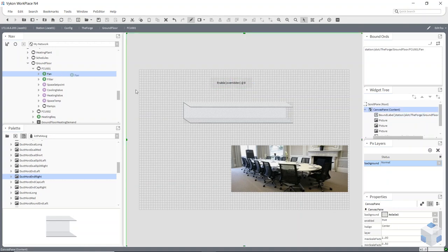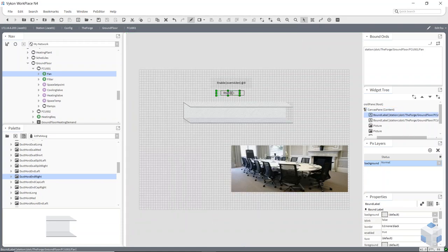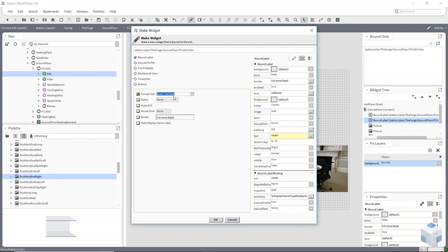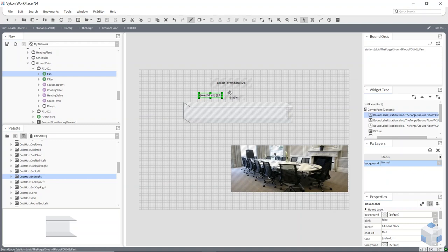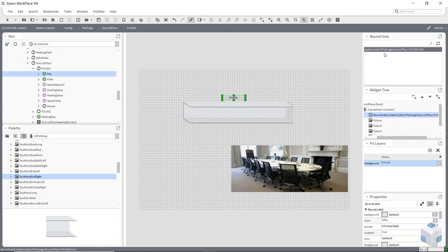If I bring that on again for the same point and change my format to 'out.value', it will then show just the value — which is what I really want for my graphic. If I bring it on again I could change the format to 'out.status' to bring in just the status. So the out value is what I wanted — I can delete the other two. In my Bound Ords I can right-click to see where the point is on the page and in the widget tree.